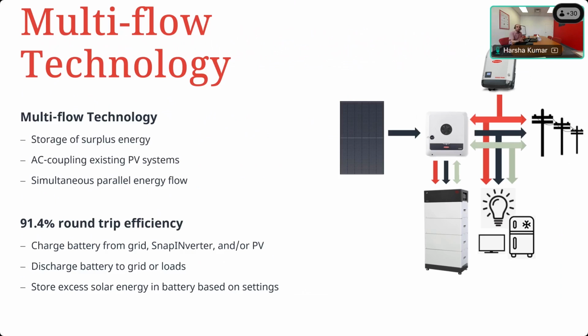That is different if they're net metered, right? Not under a microFIT, for example. So just keep that in mind - if you're connected to the grid directly and not to your electrical panel, this doesn't work. This is only behind the meter, so you have to be sharing the same panel board. It won't work with a net metered system.